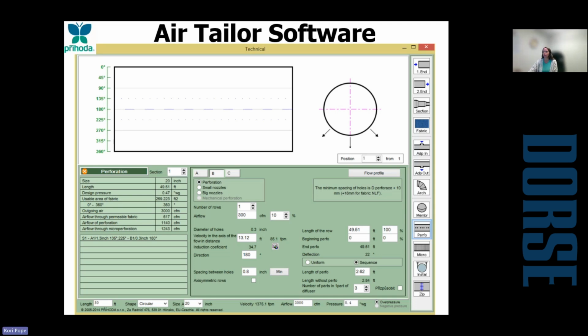So one way that we can do that is as we're putting in your perforations or nozzles, we can actually put in the distance from the duct, and we can see specific velocities, the feet per minute that the air will actually be at said distance. So when we're looking for cooling and heating as well as in the ventilation mode, we can ensure that what we're giving you is exactly what you're going to receive once it arrives on site.